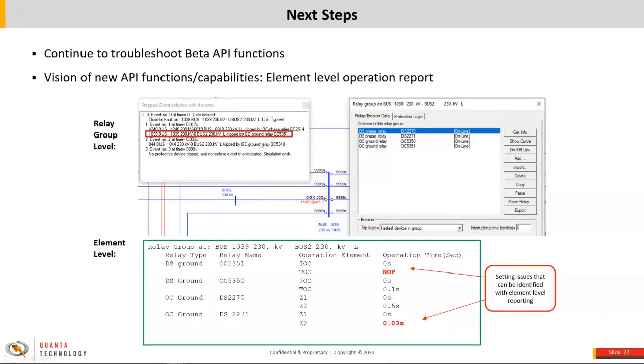For example, regarding the step event analysis: if you haven't used this functionality in one-liner before, the current version generates a string-formatted report at the relay group level — it tells you that on this relay group, this OC ground relay OC 5351 operated. In our vision, we hope the future will have a more detailed element-level report. For instance, issues at the relay group level can be hidden: the IOC operated immediately, but the TOC does not operate because the pickup is set too high and it can't even see a closing fault, or a zone 2 element timer is set too short so it operates right after zero seconds.